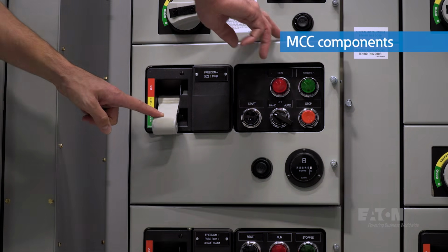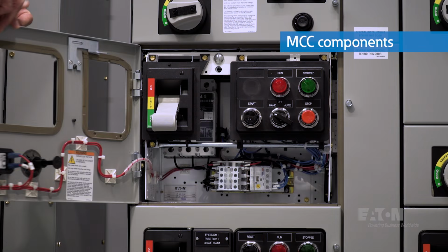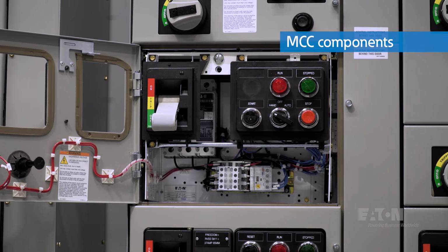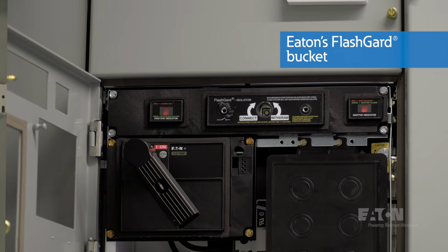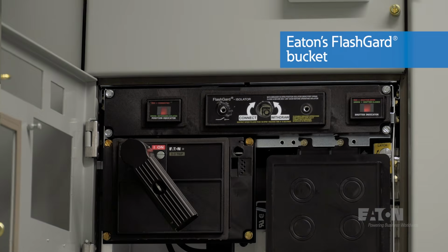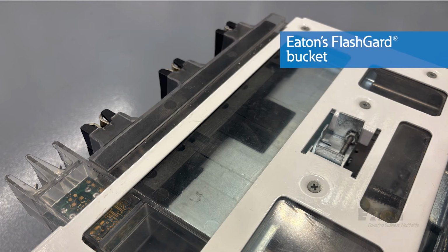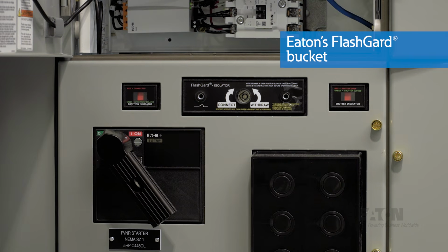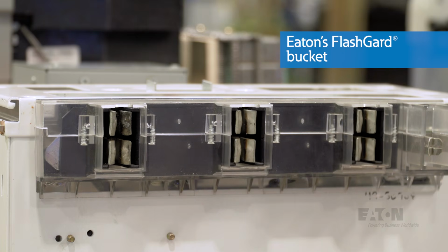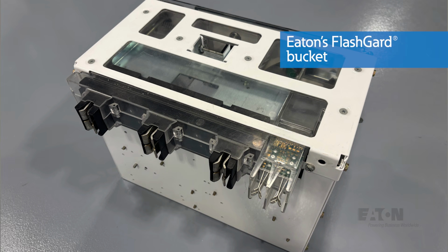Now that we have covered the overall enclosure, bus system, and wireways, let's discuss the actual buckets themselves that may be bolted in or removable, and the components that get installed inside the buckets. There is also a unique option for Eaton's FlashGard bucket that adds an additional level of personnel safety. Specifically designed bus stabs, insertion guides, handle mechanisms, wrapper, terminal blocks, and safety interlocks are added to form a standardized plug-in unit that meets the highest safety standards.